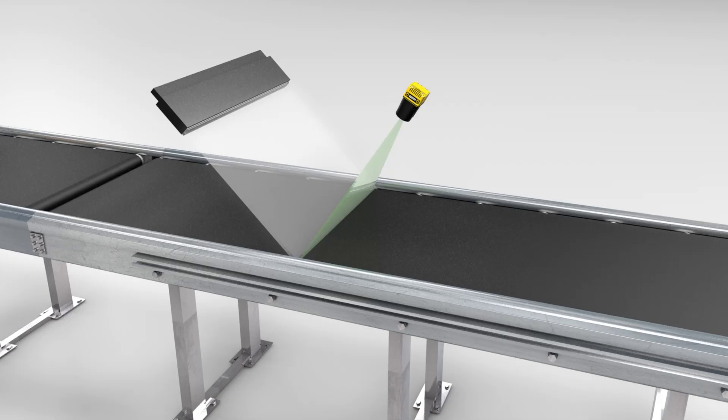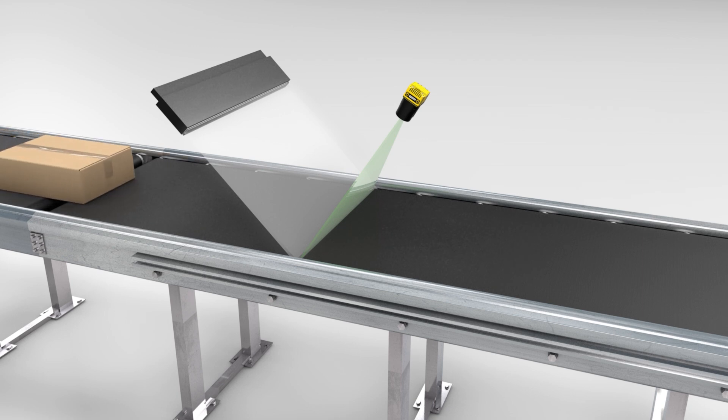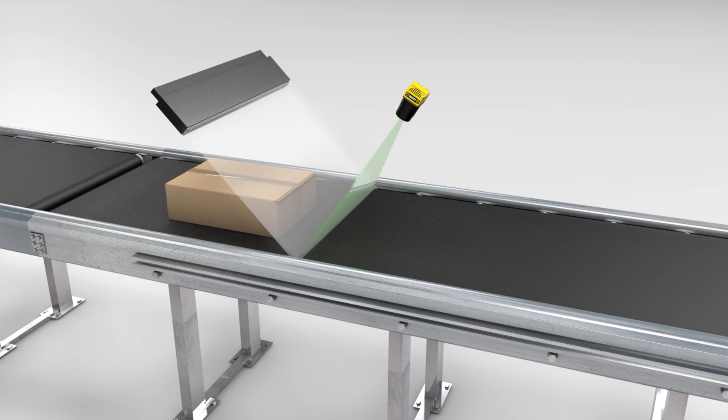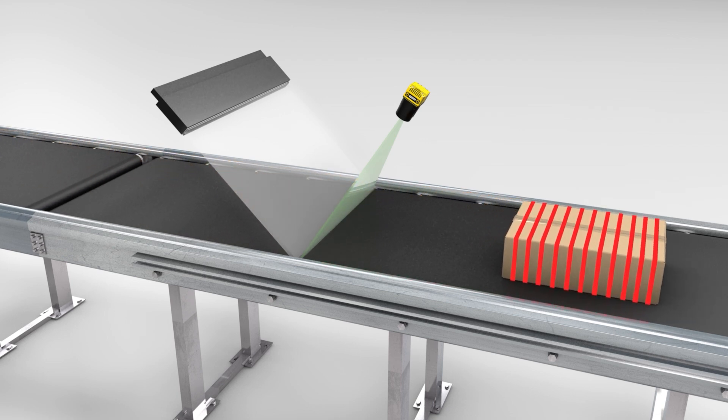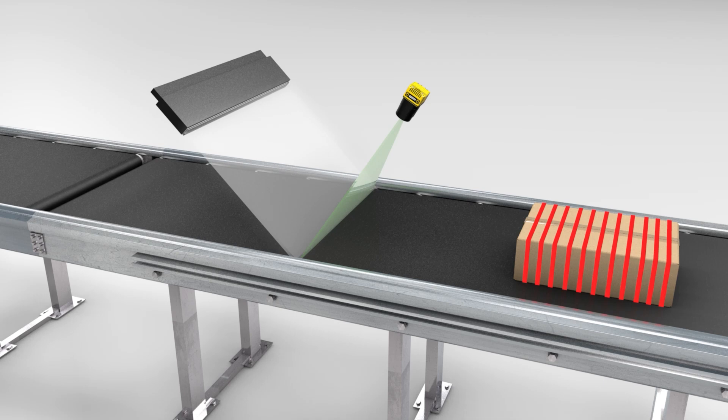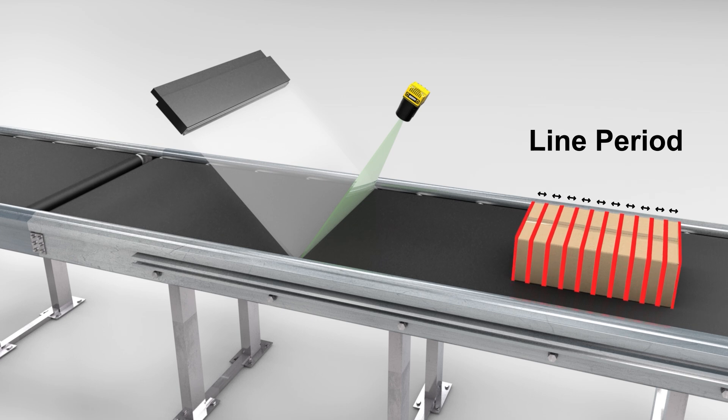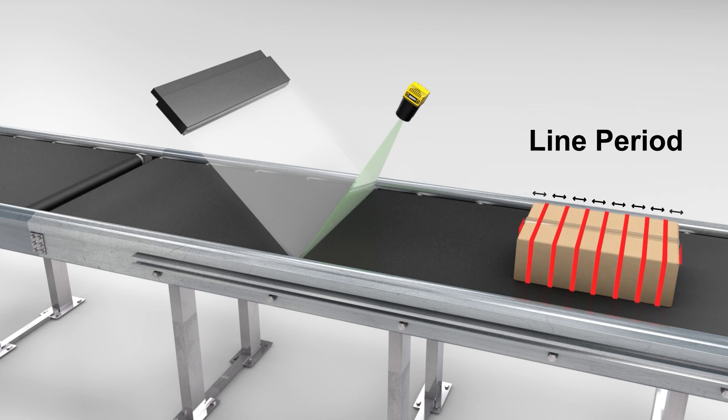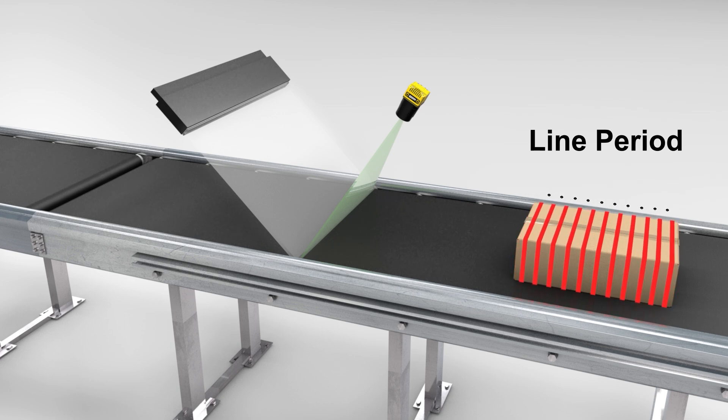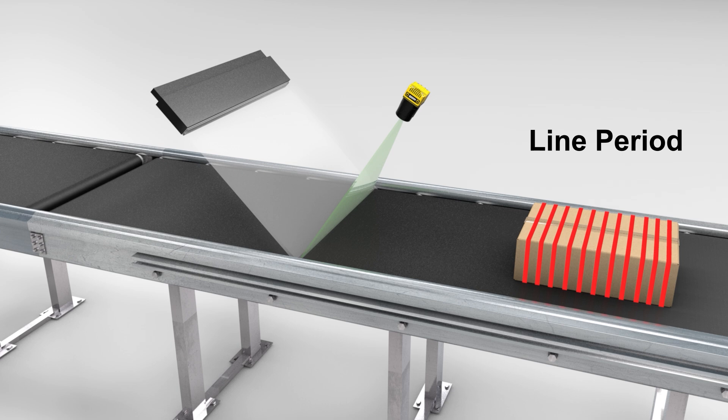With software encoder selected, no external signals need to be connected to the InSight 3800 line scan system because it uses an internal clock to provide this signal. The line period parameter is used to specify the interval in microseconds at which to acquire lines. A new line is acquired based on that time interval, regardless of the physical motion of the machinery. The software encoder is useful when the speed of the conveyor belt is consistent since no physical encoders must be installed and integrated.